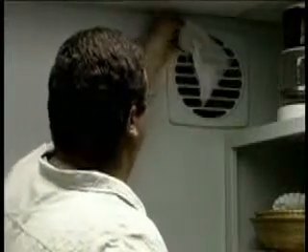Continue the walkthrough inspection inside. Now you are looking for indications that the ventilation system is functioning, signs of moisture damage, evidence of pollutant sources like mold or housekeeping supplies, general cleanliness, or anything which might impact the air indoors. Remember to use your checklist to guide your walkthrough and note any relevant observations on this sheet or on a floor plan of the school.